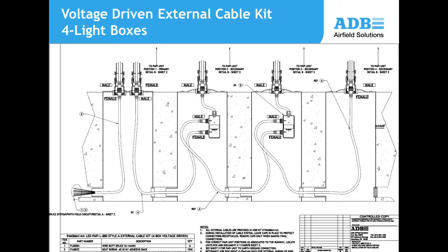The incoming power and any control signals — such as for interlocking with another series circuit — connect to the first PAPI unit. Pre-connectorized cables then run up to connector boxes and on to each successive PAPI light unit in the string.